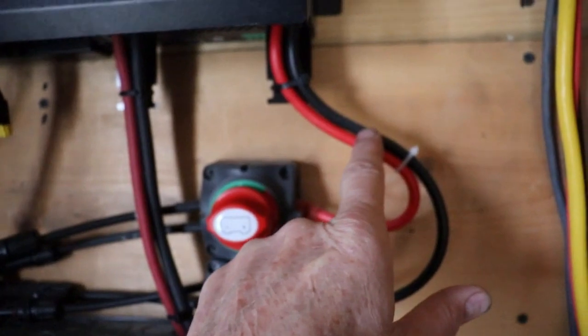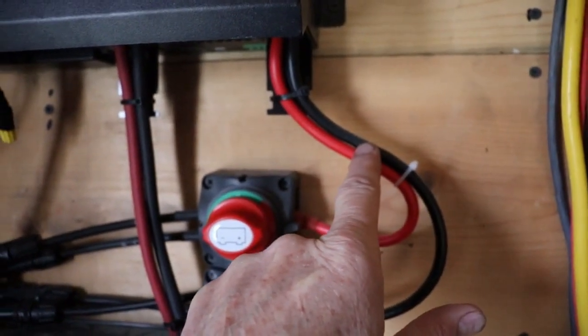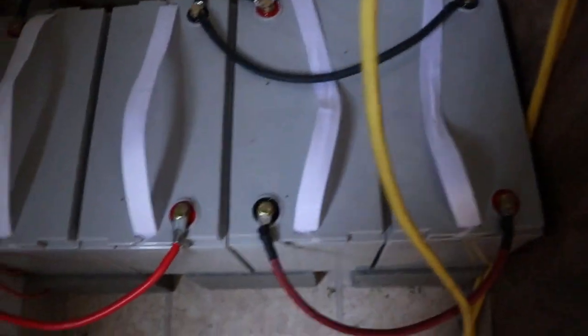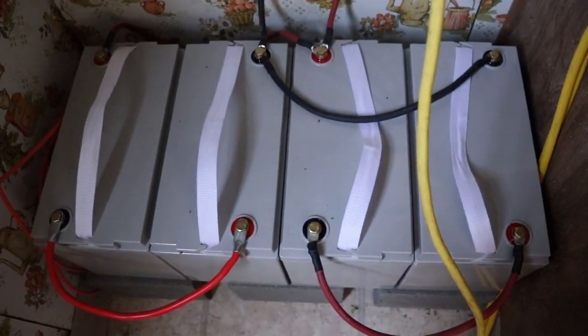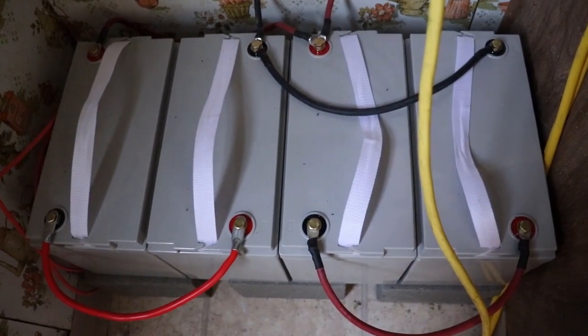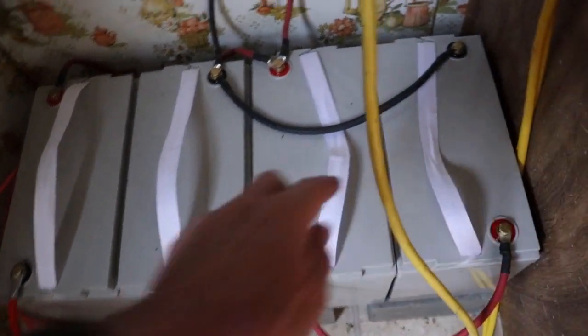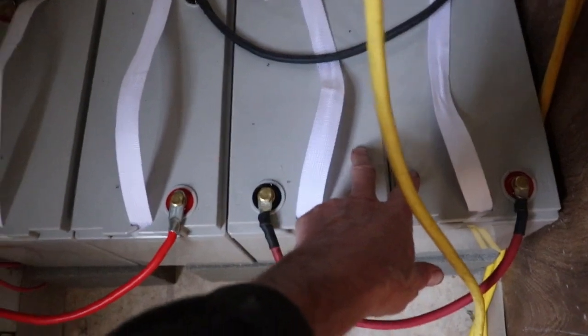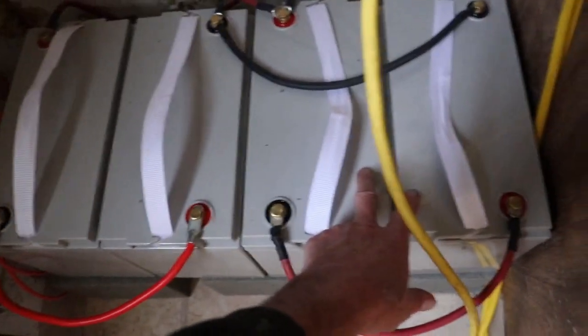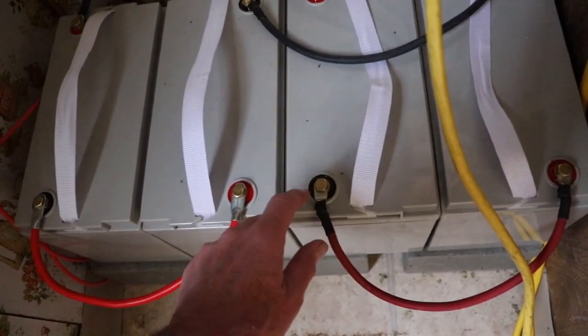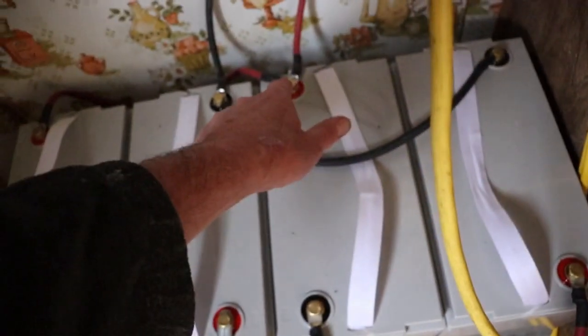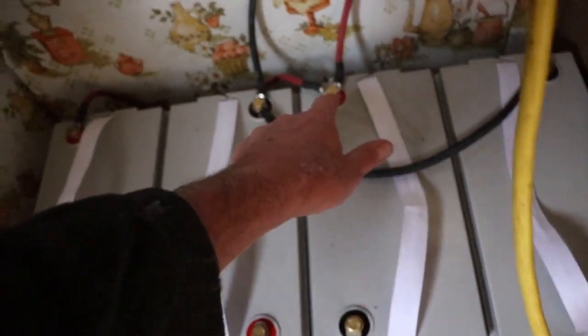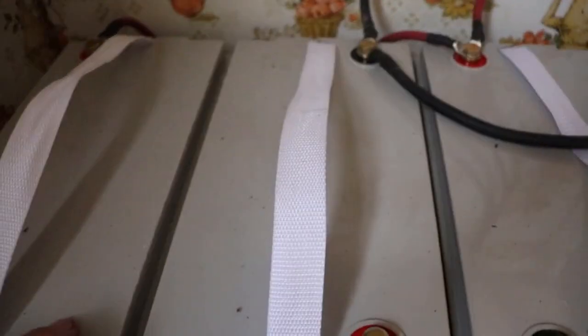This is for the array, for the solar panels coming in. Follow it down - I have four 100 amp hour LiFePO4 batteries, lithium iron phosphate, and there's two in series to make 24 volts because it's a 24 volt unit. You connect the positive to the negative, and then there's your ground, and there's your hot wire, your voltage DC positive.